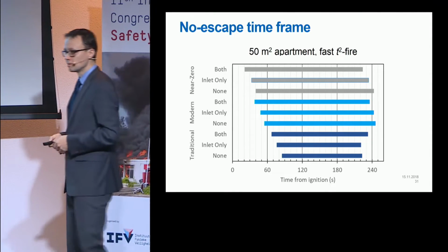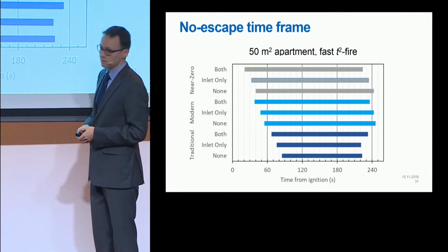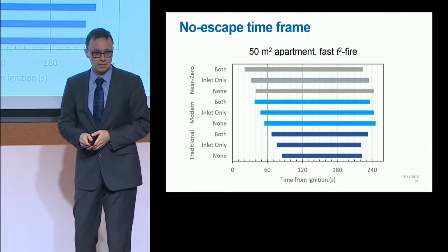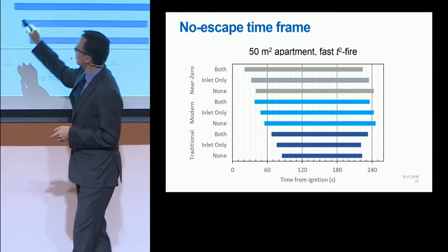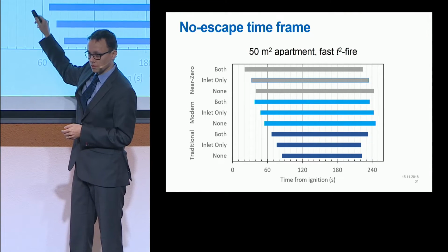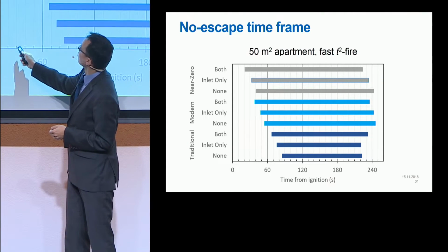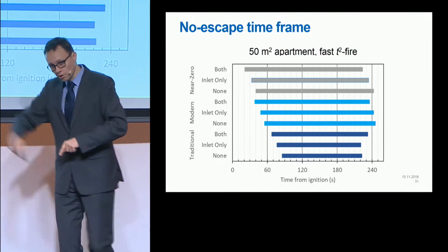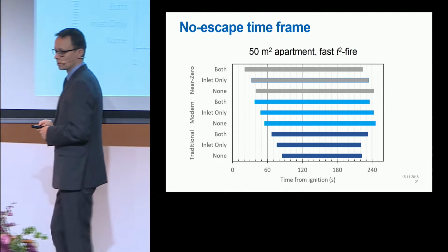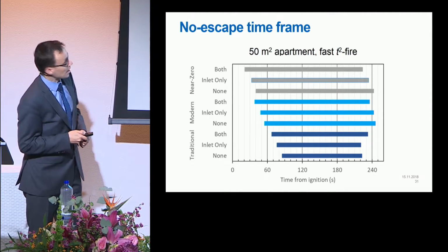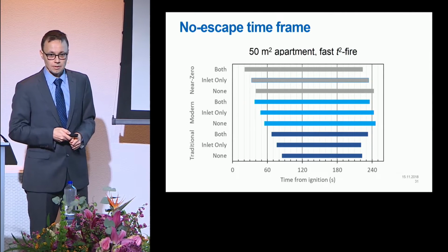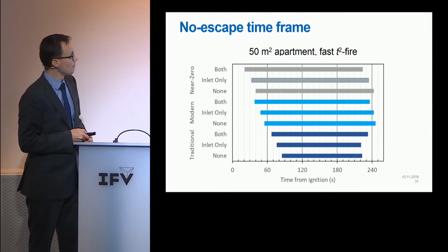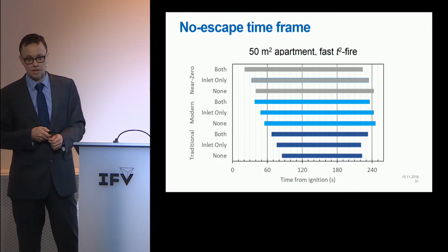Can you hold your breath for that time? Maybe not. Going to modern or near zero buildings, the time that you have available before 100 Pascal goes down to less than 30 seconds. Okay, and now we measure the time from the actual well-defined ignition of a fast T-square fire. But those are pretty short times, and fairly long time spans to wait.